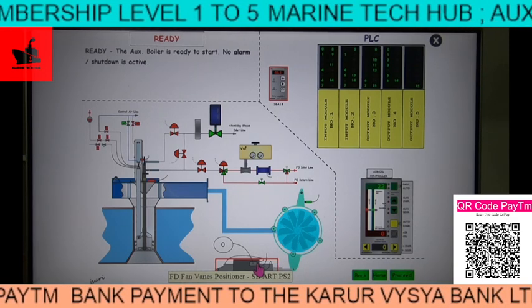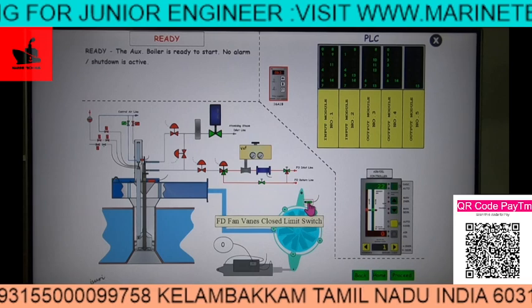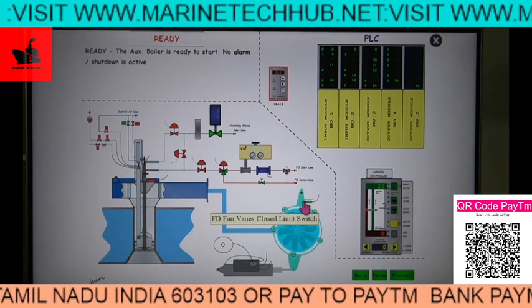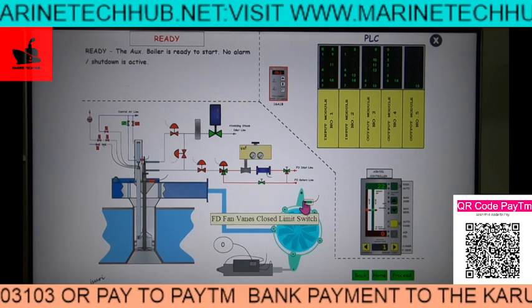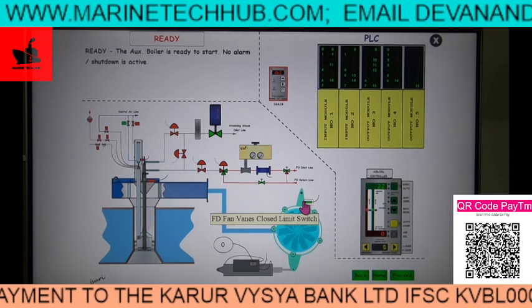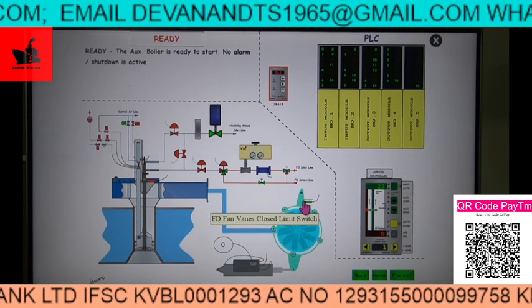Another component is the FD fan vane positioner, also made by Siemens. When the FD fan is moving, the spindle will move and indicate the position — whether the FD fan is in the closed position or not. There is a component called the FD fan vanes closed limit switch. This limit switch will confirm the fan is in the closed position, because the FD fan will start only in the closed position, not in the open position. This interlock is kept to reduce the starting current. Once the fan starts, it will begin to open slowly after purging.